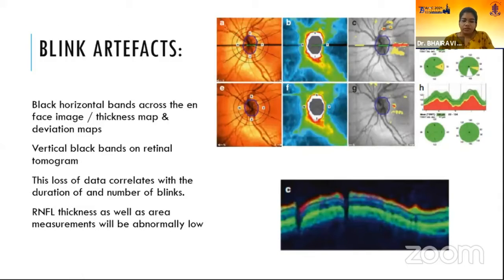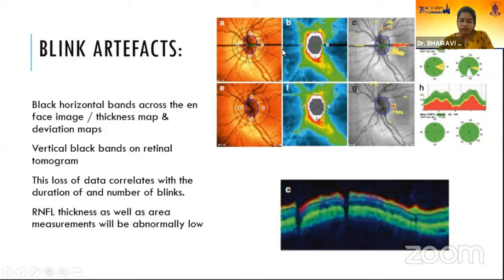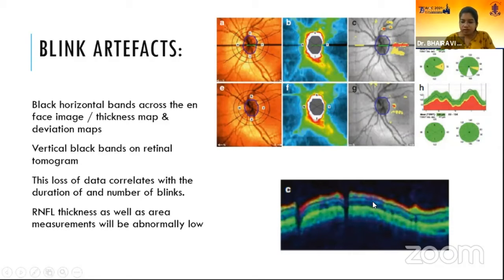Blink artifacts are caused when the patient blinks during scan acquisition. They can be seen as black horizontal bands on the thickness map and vertical black bands on the retinal tomograph. The loss of data correlates with the duration and number of blinks. The RNFL as well as area measurements will be abnormally low in these areas.